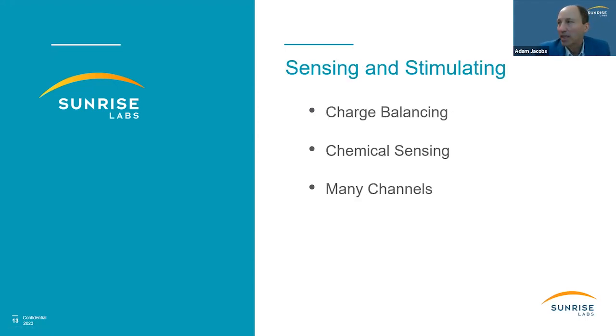Sensing and stimulating is always an interesting topic, and it's a very dynamic field. There's lots of research going on in sensing and stimulating. We'll start with stimulating. One of the interesting things is, if you're stimulating something, you typically try to use what's called biphasic stimulation, which means you go positive and negative, which means you're putting the charge out there and you're taking it back. And the reason is because you don't want there to be a buildup of charge out in the tissue, which can cause chemical changes because you're now providing a voltage into the tissue, but you can also affect your electrodes. You can have electrode degradation.